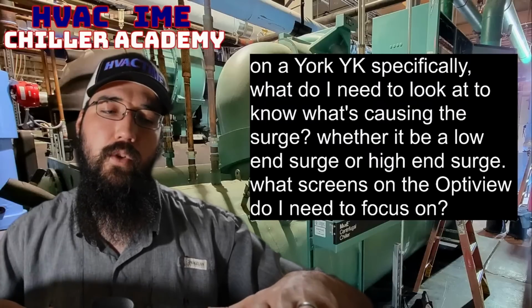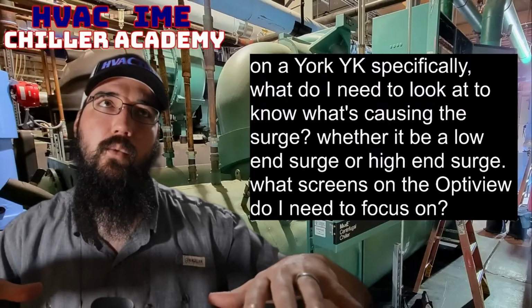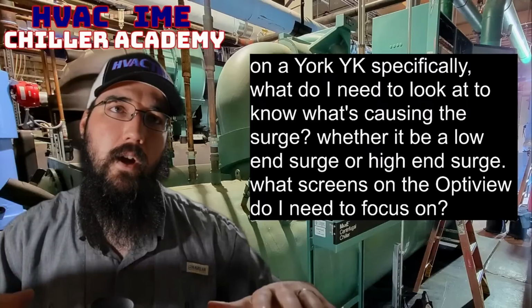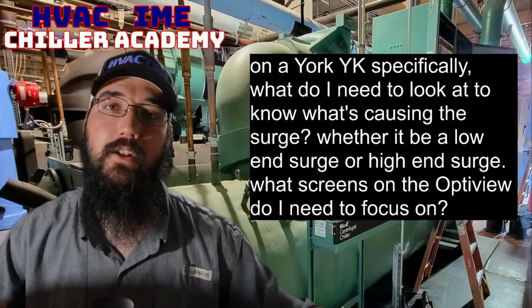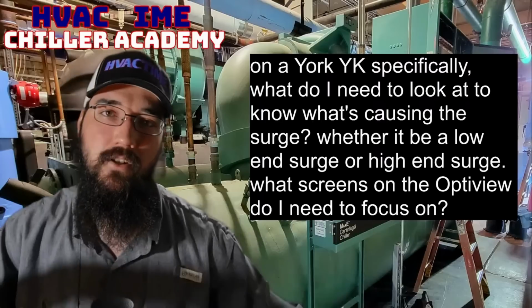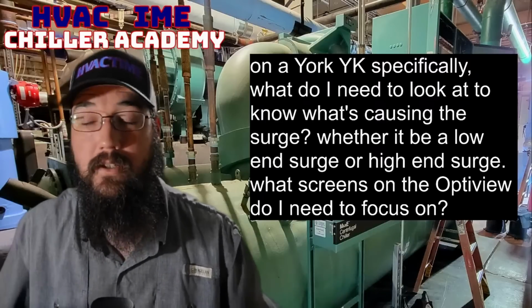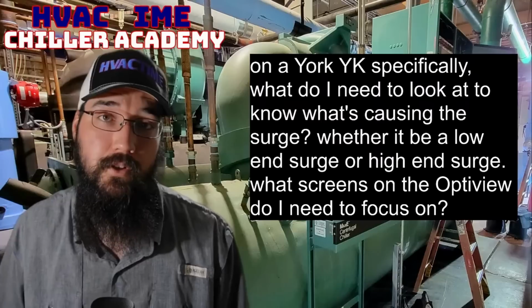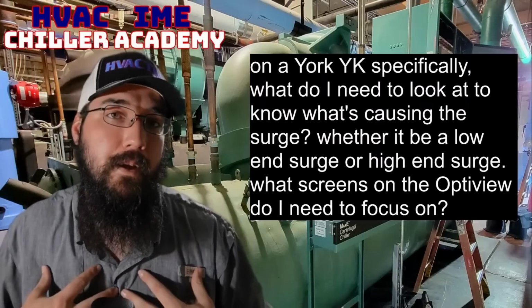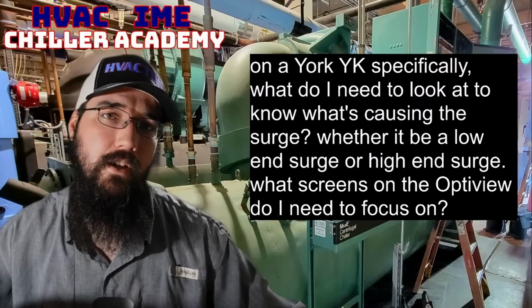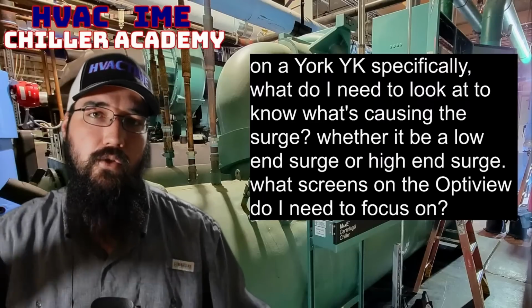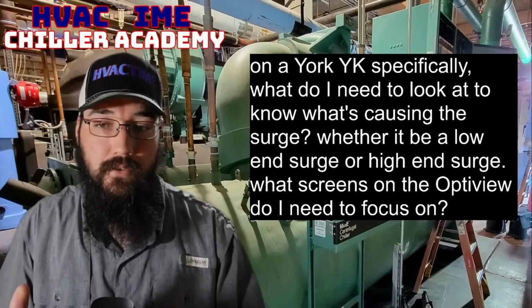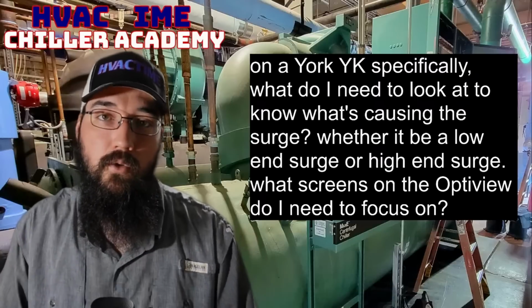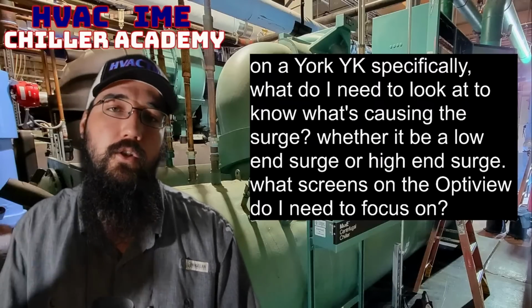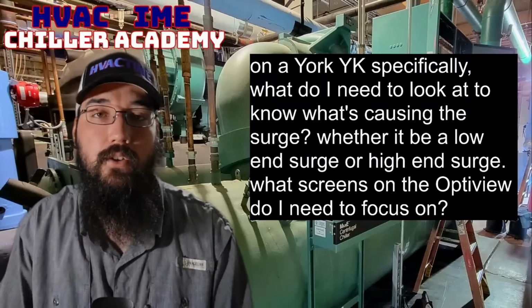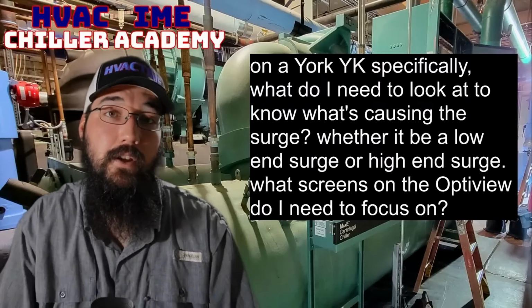And so when your flows or your load aren't quite right, or your temperature entering the heat exchangers just aren't quite right, it's not that hard to push a YK into a surge state compared to some other chillers that in my opinion I have seen be a little more forgiving with the way that they adjust to their surge curve. So yes, start with those basic screens. You need to know what your temperature values are, and you can use that VGD screen if it exists. If you don't have one, then it's not there to be helpful to begin with.